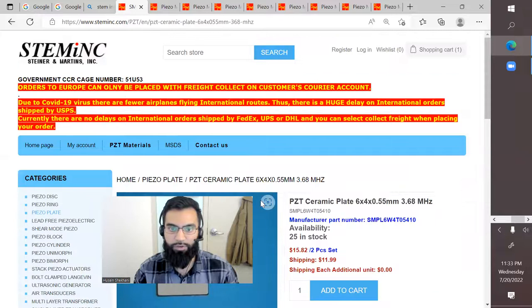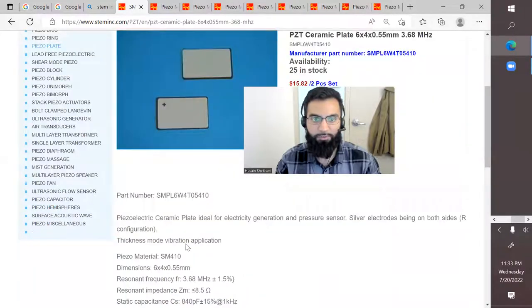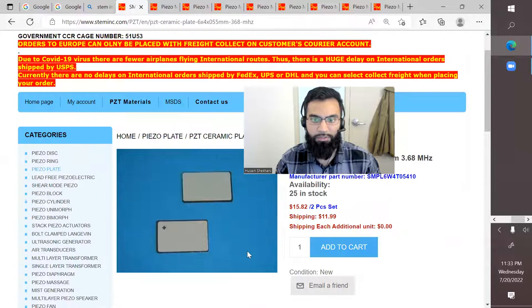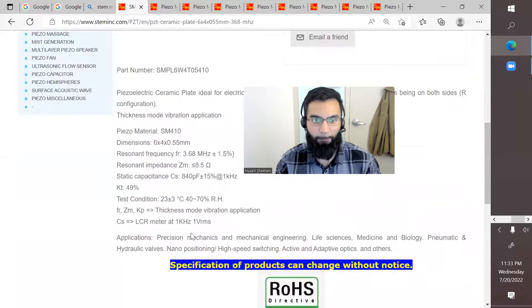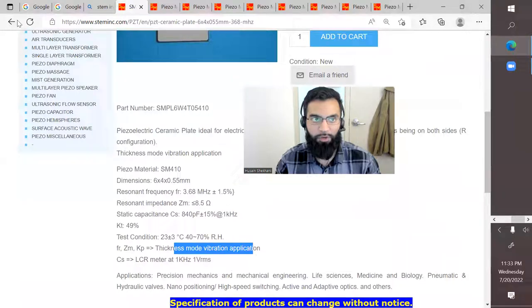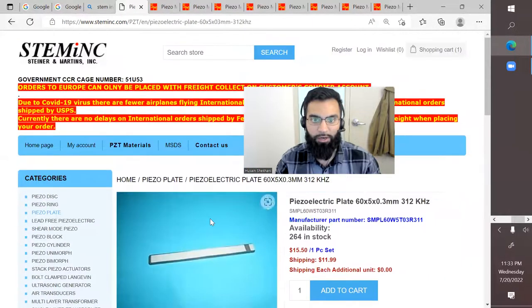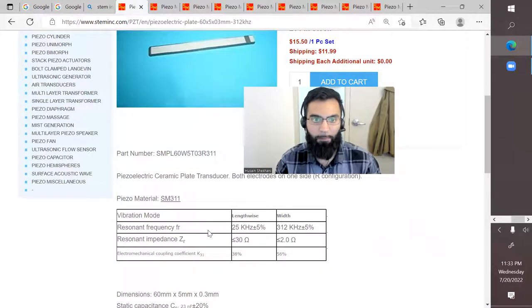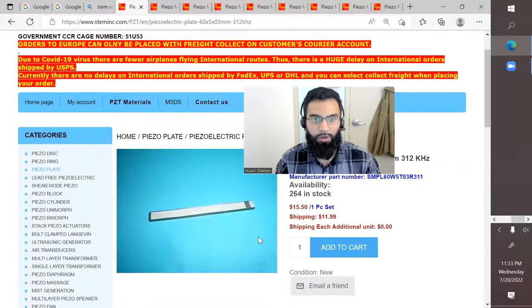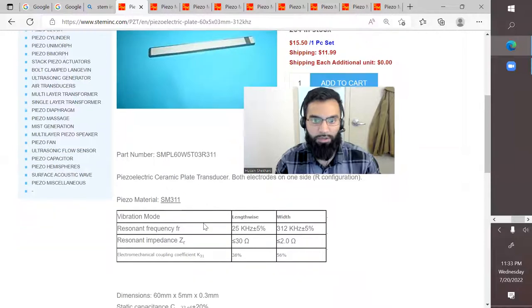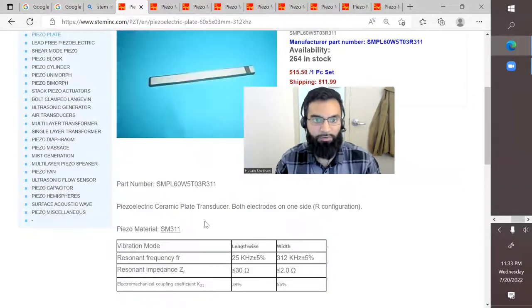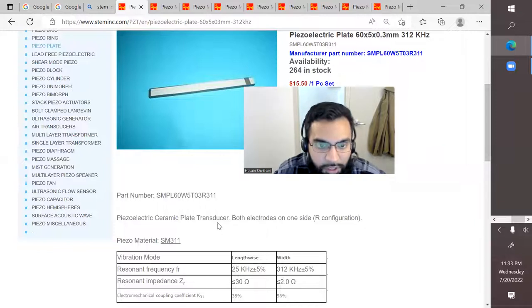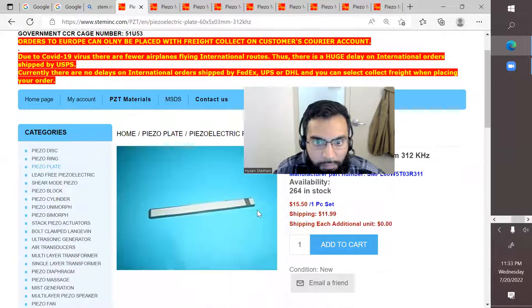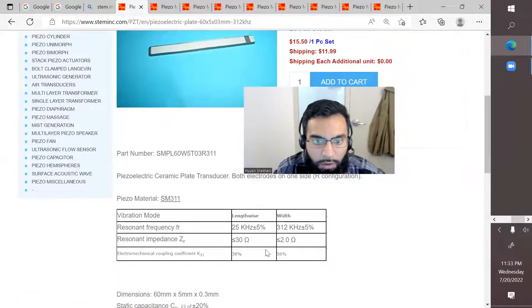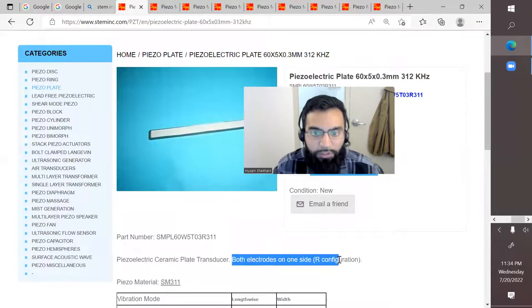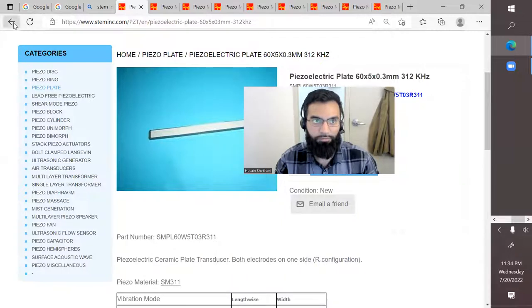Make sure, try to ensure - I think for all these products it's pretty standard for it to be thickness polled, thickness mode vibration. But that one was an oddball here, this guy, where it actually was not thickness polled. So I would see piezo ceramic on both sides. I would actually go out and ask them whether this is thickness polled. How this is actually both electrodes on one side.